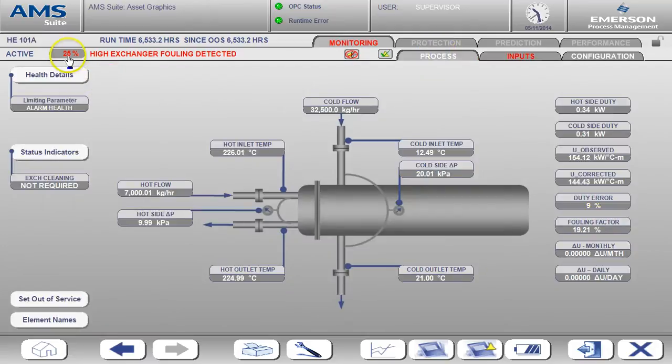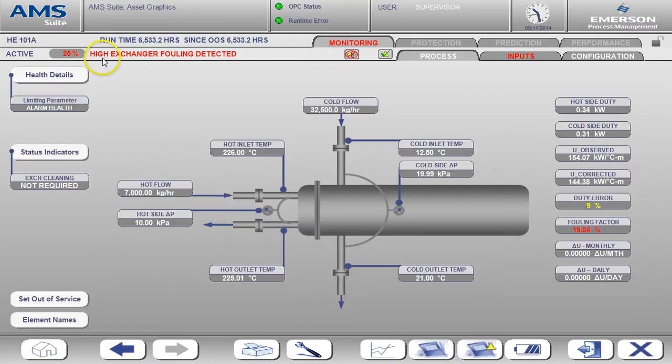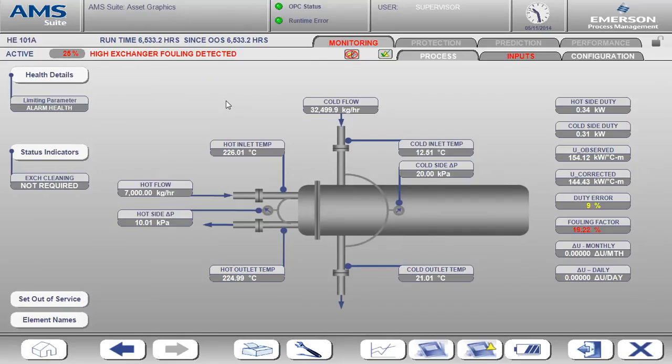Now on this screen we see the health is 25% and the high exchanger fouling detected text is shown. Also the fouling factor is flashing red to indicate the value is high.